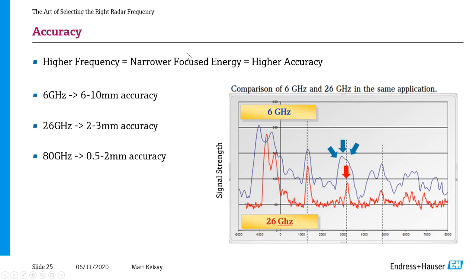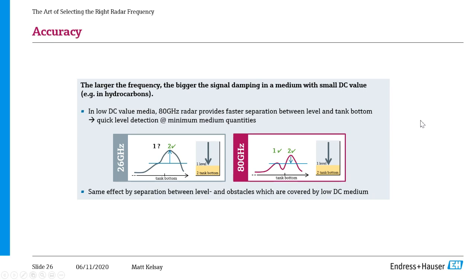that peak. If you look at the red line, it's more representative of a 26 gigahertz radar. So you can see the signal return is a much sharper peak. That just leaves less room for error for the radar to pick the wrong point along that peak. That's how you can get down into the 2 or 3 millimeter accuracy range. I unfortunately don't have an overlay of an 80 gigahertz radar, but you can imagine it's just an even sharper peak than that red line. And again, that allows us to increase that accuracy to 0.5 millimeter to about 2. Okay, we can go to the next.